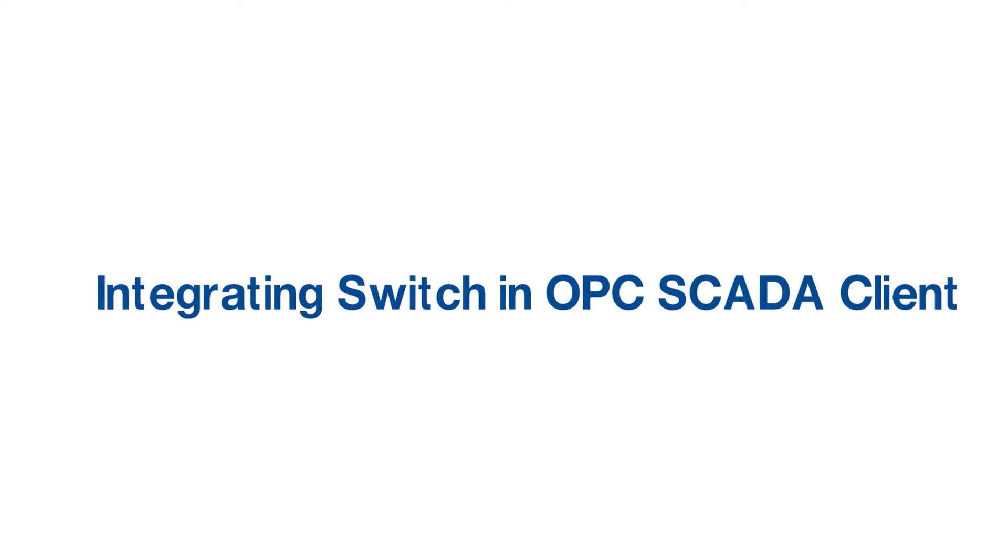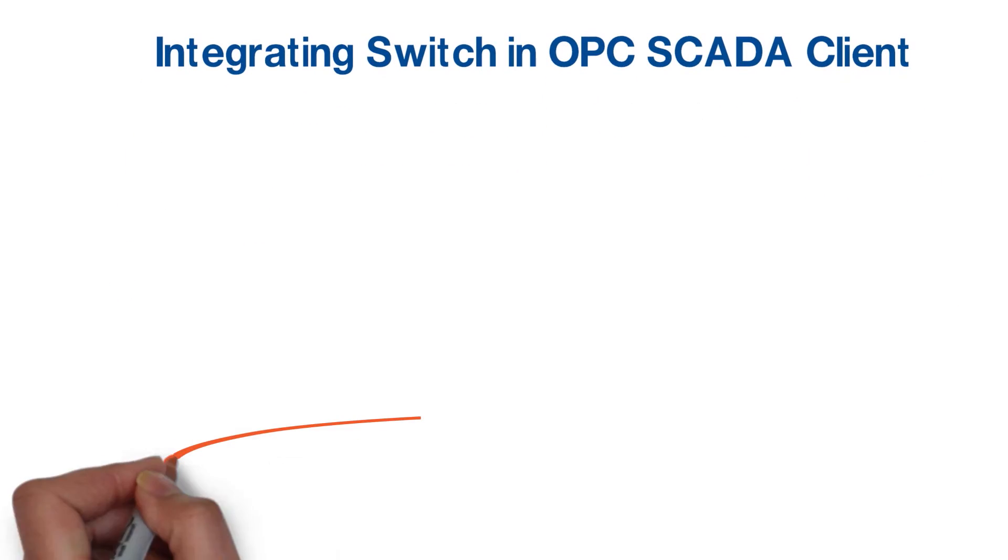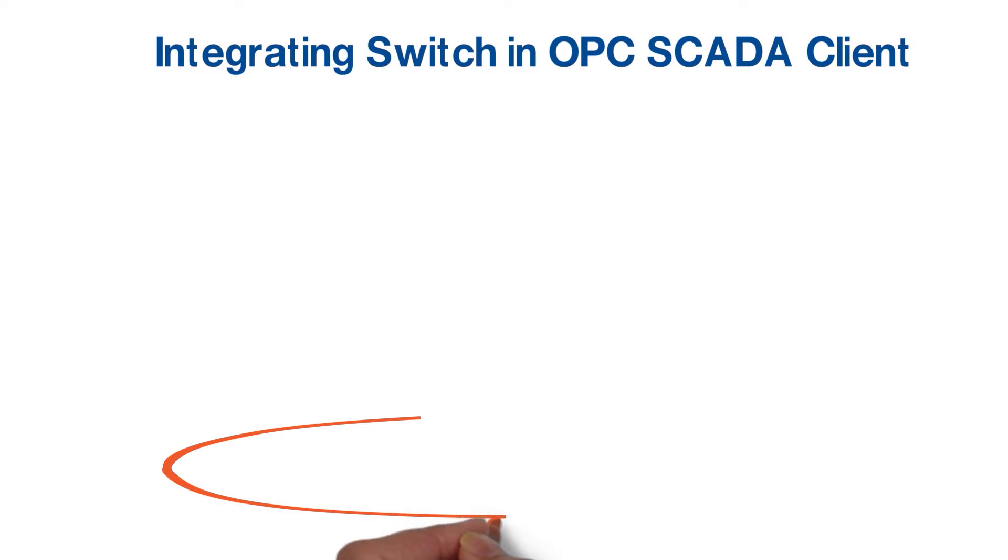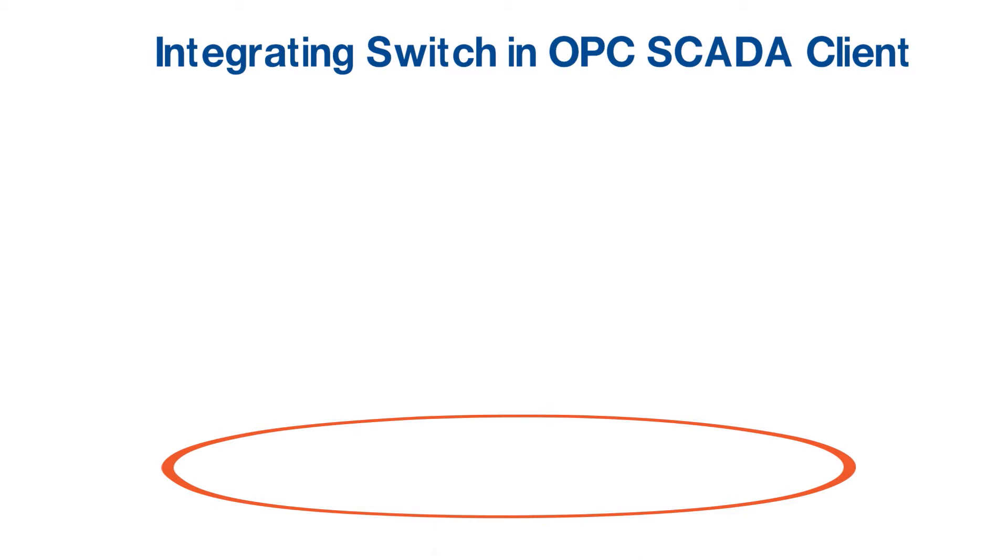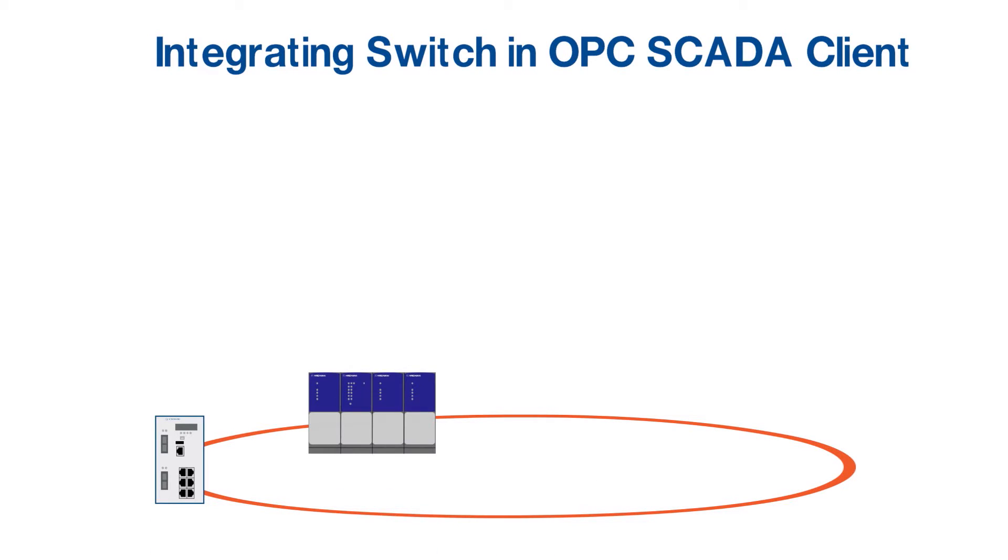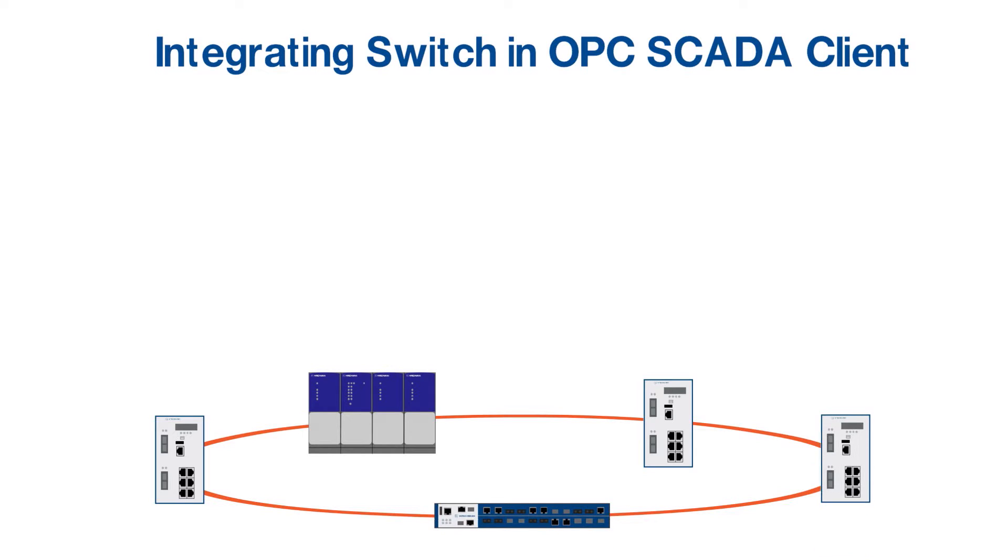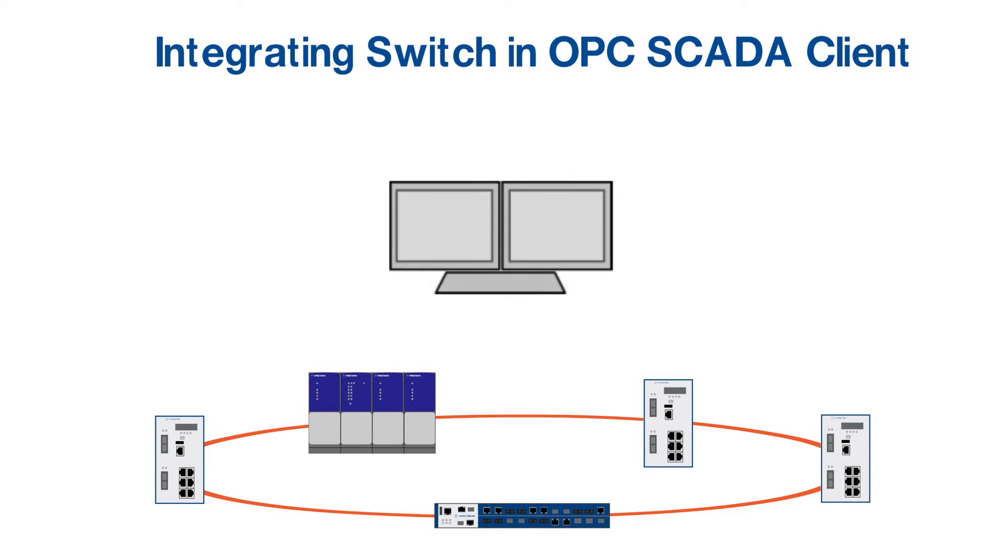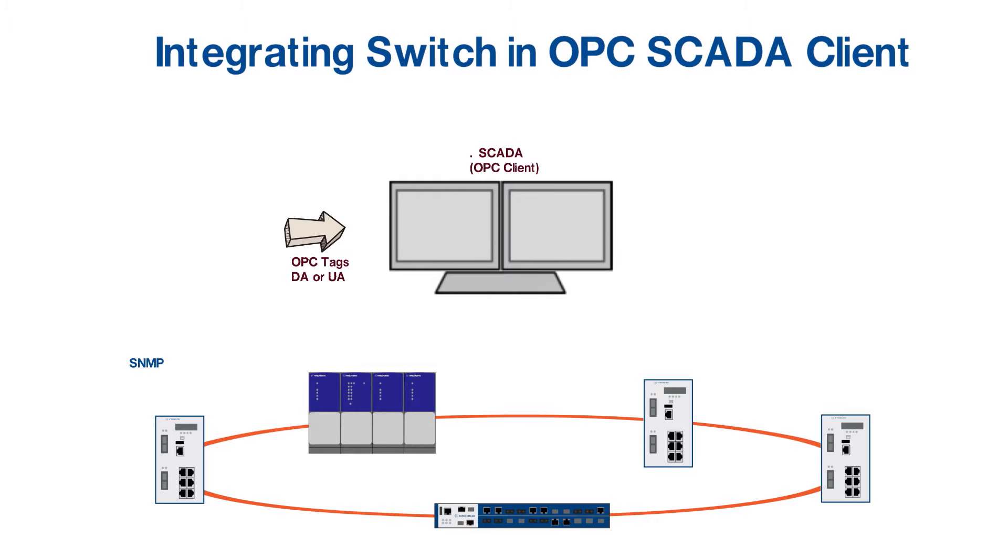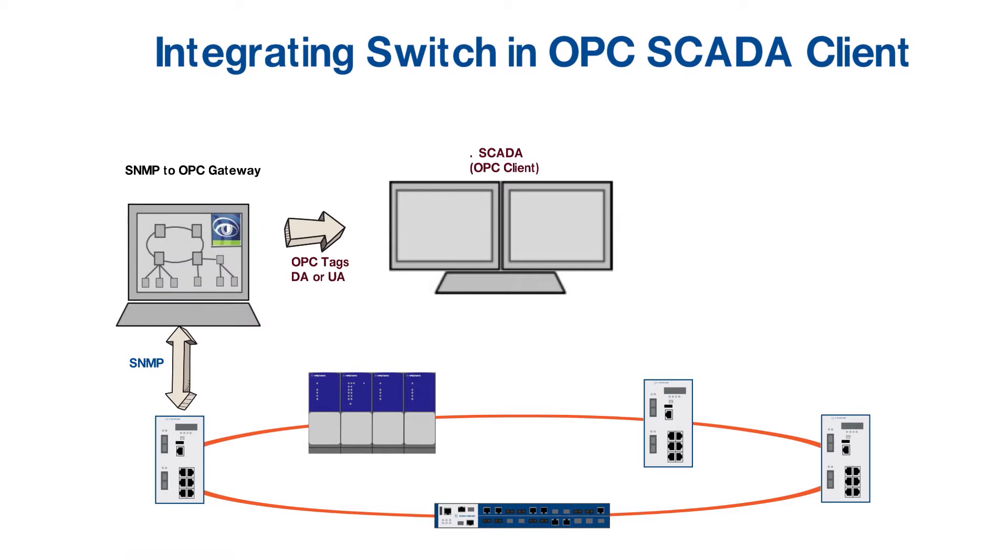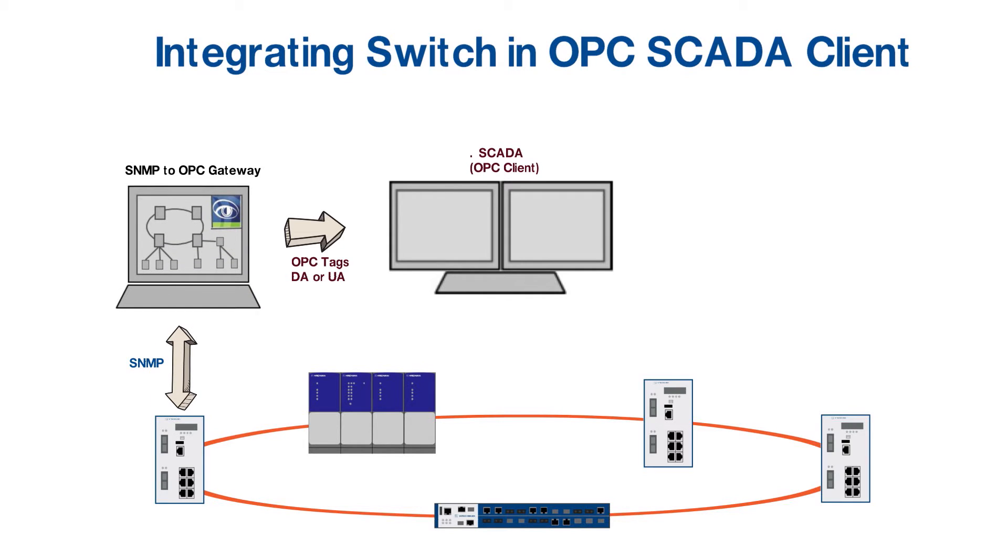Integrating industrial network components and monitoring their health in SCADA systems is a major requirement for many customers. In our application at Dierman Industries, we have multiple switches, routers, and other components connected over optical fiber and copper cables. The health of this network needs to be monitored in automation systems. The central SCADA system is based on OPC tags, whereas the network components are based on Simple Network Management Protocol or SNMP.